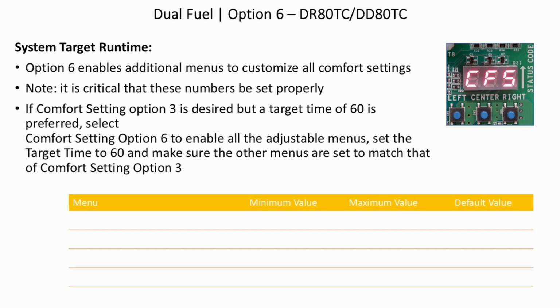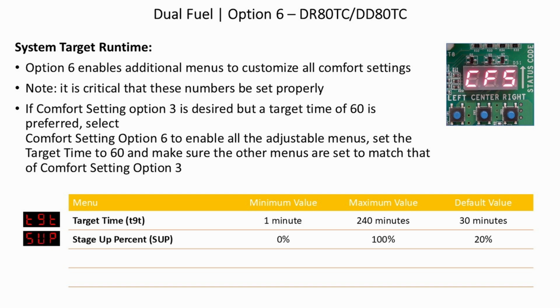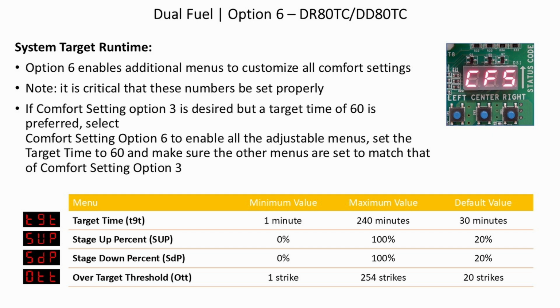Available adjustable menus are target time, minimum value 1 minute, maximum 240 minutes, default is 30 minutes. Stage up percent, minimum is 0, maximum 100%, default 20%. Stage down percent, minimum 0%, maximum 100%, default 20%. Over target threshold, minimum 1 strike, maximum 254 strikes, default 20 strikes. Under target threshold, minimum 1 strike, maximum 254 strikes, default 20 strikes.